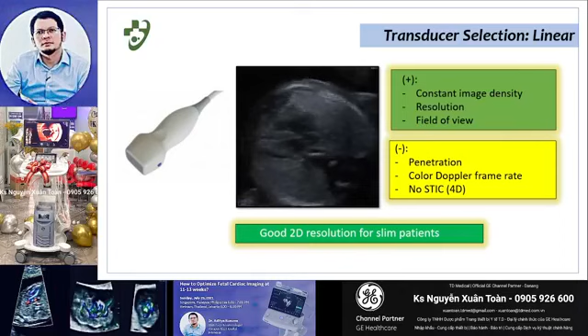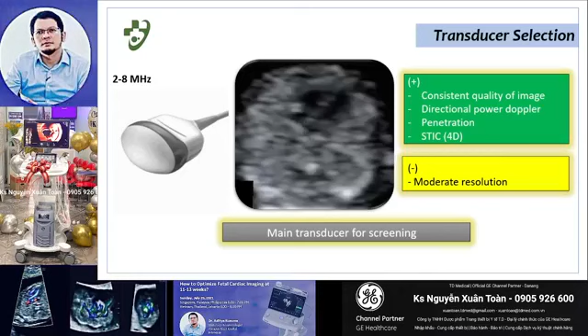And this is the probe as the main transducer for screening. Why? Because it has consistent image quality, directional power Doppler, good penetration, and we can use STIC with this probe. But the downside is moderate resolution. And this is the best probe that we can use for the first trimester. This is for targeted screening.